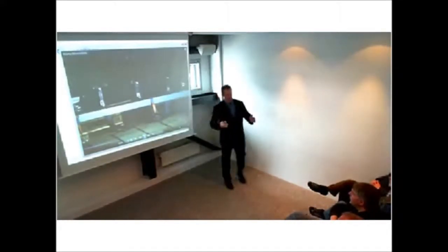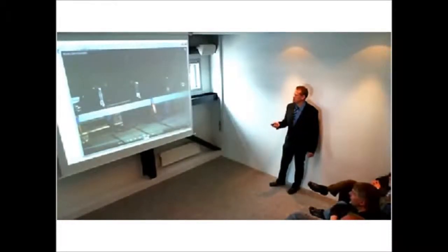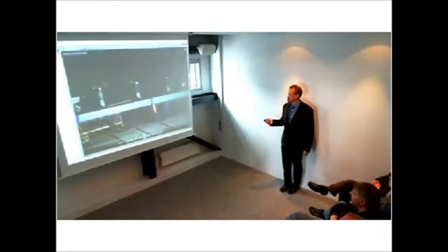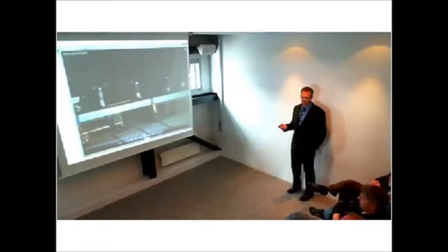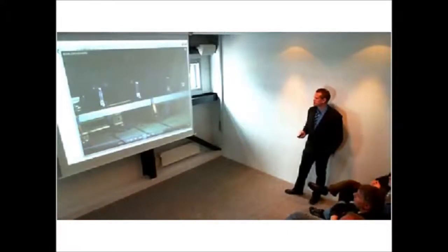You can see now the cables are going in opposite directions from each other. And this is 16 cables with full short circuit on this side, and the load is going in there. So this is just to test this cable clamp, to see if it can keep up with this current. Yeah, you can see this clamp moves a little bit, but it passed the test.